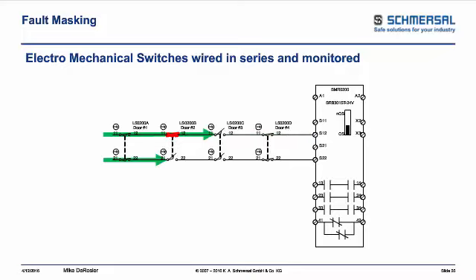You could be opening up 2, 3, or all 4 doors to refill something or clear a process or something jammed that you had to clear out. They go and open up door number 3. Well, what did door number 3 just do? It cleared the fault. The controller saw both channels clear out now.